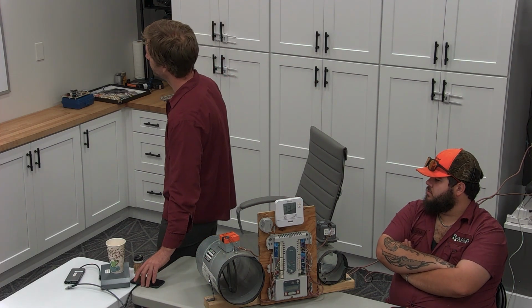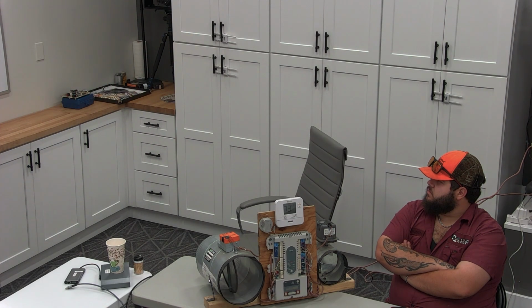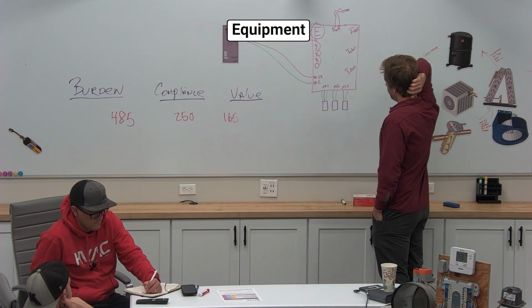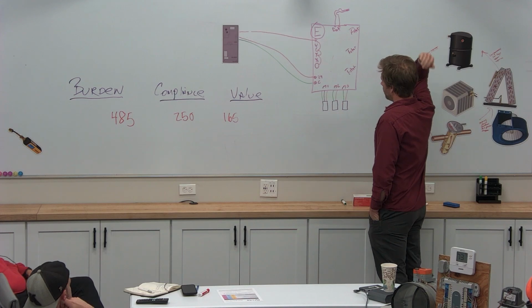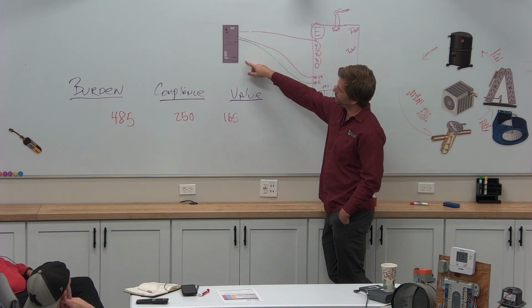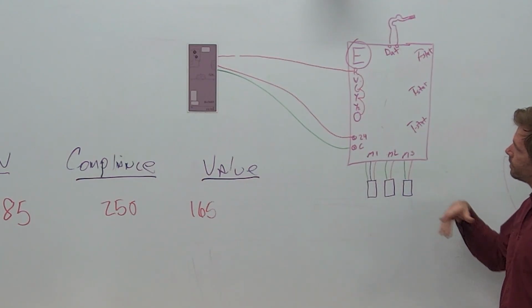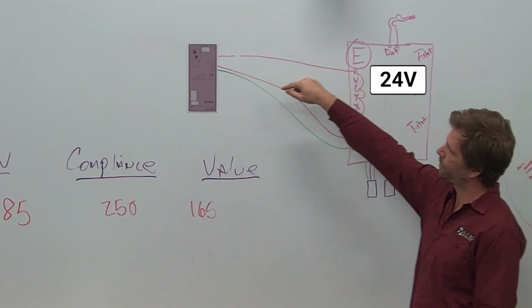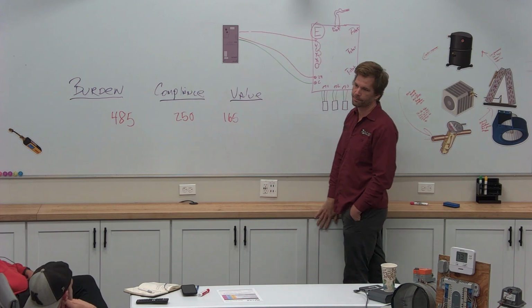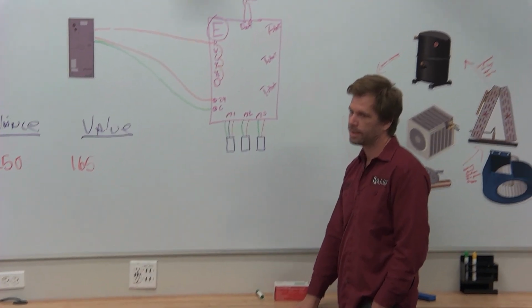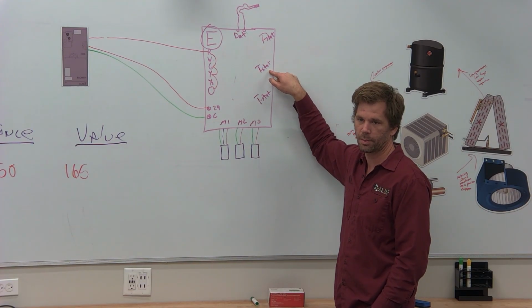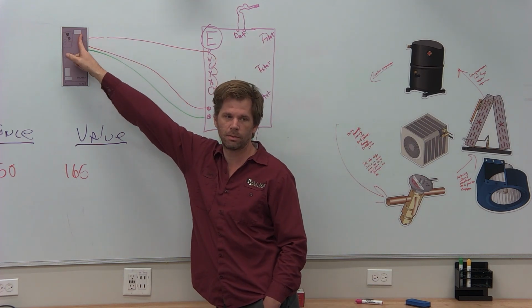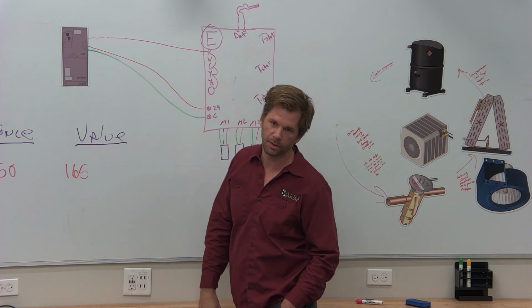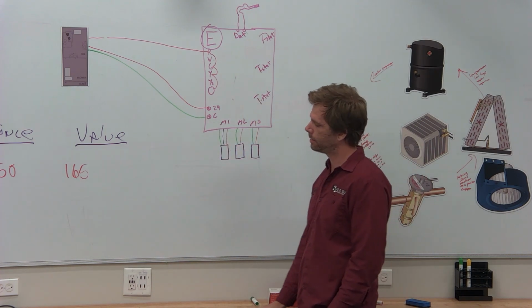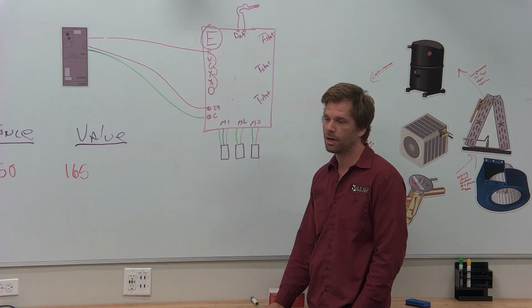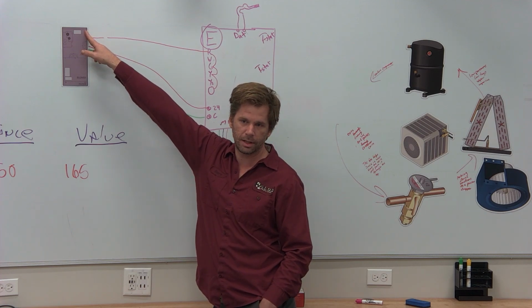All right, let's talk about understanding the damper system. What's the E stand for up here? Equipment. That's right. Our equipment is our air handler and condenser and control system. And the equipment is powered by 24 volts that comes from the factory transformer inside our air handler. So if we want to pull in our condenser contactor, we can't use yellow from one of our thermostats and wire nut it to yellow in our air handler because it's a completely different 24 volt power source. The yellow tied in at our condenser is going to have common coming back to the transformer that comes from the factory of our air handler, right?